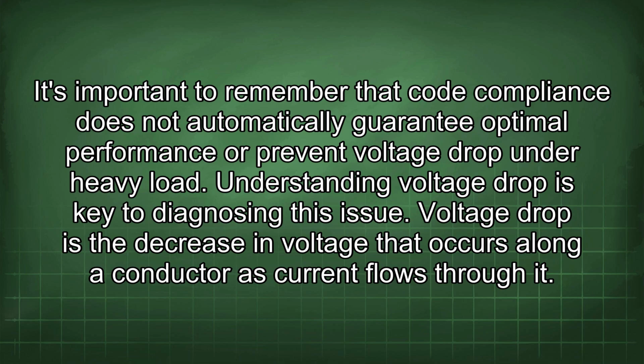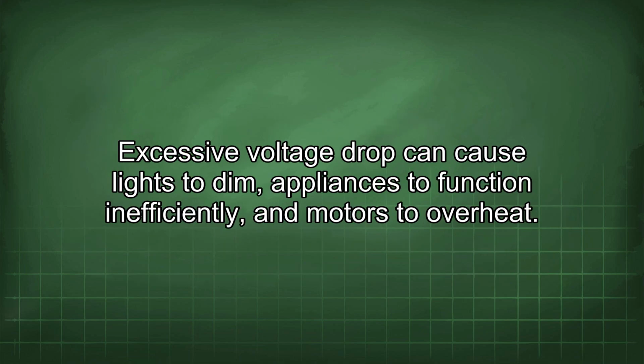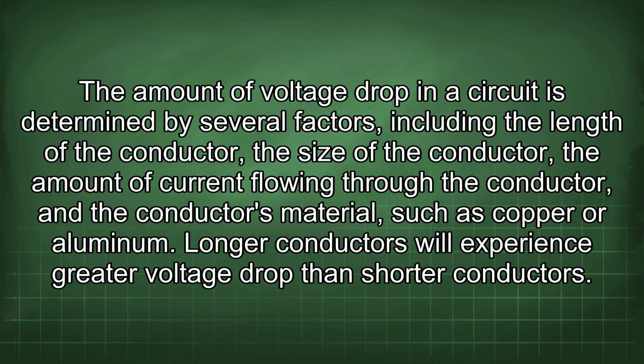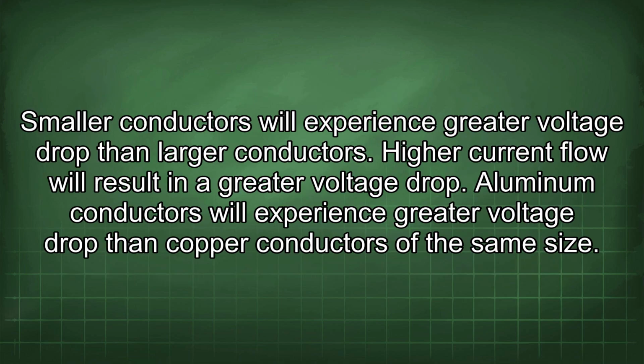Voltage drop is the decrease in voltage that occurs along a conductor as current flows through it. Excessive voltage drop can cause lights to dim, appliances to function inefficiently, and motors to overheat. The amount of voltage drop in a circuit is determined by several factors, including the length of the conductor, the size of the conductor, the amount of current flowing through the conductor, and the conductor's material, such as copper or aluminum. Longer conductors will experience greater voltage drop than shorter conductors. Smaller conductors will experience greater voltage drop than larger conductors. Higher current flow will result in a greater voltage drop. Aluminum conductors will experience greater voltage drop than copper conductors of the same size.